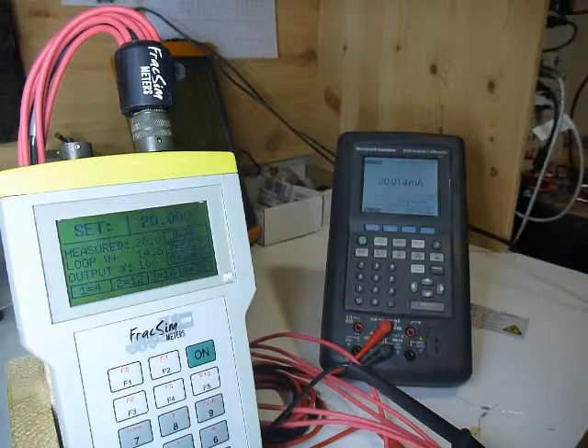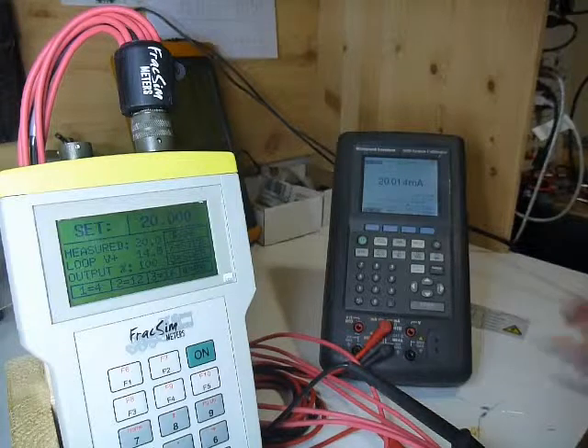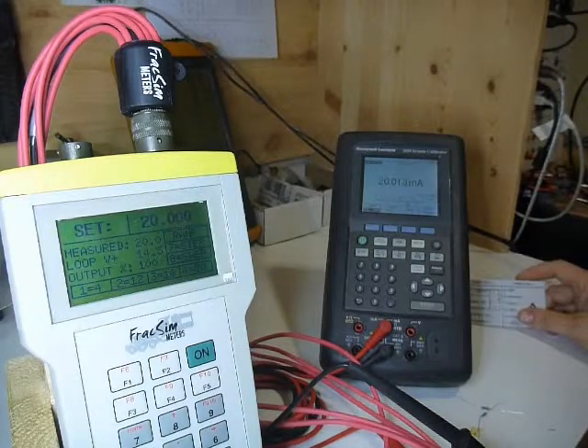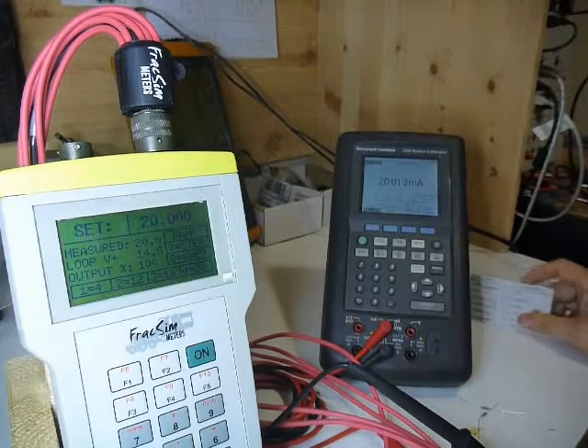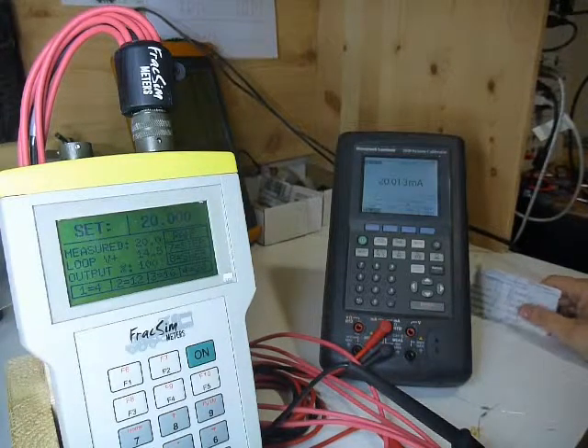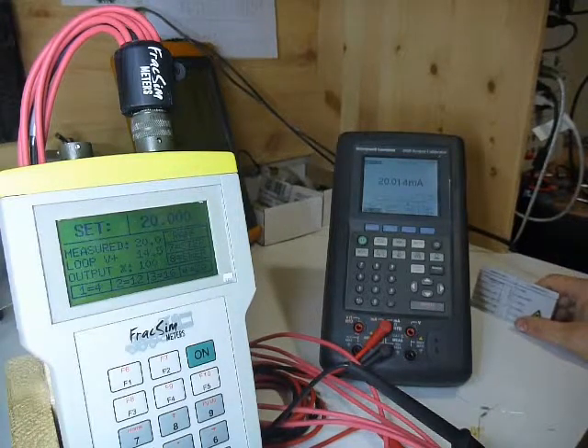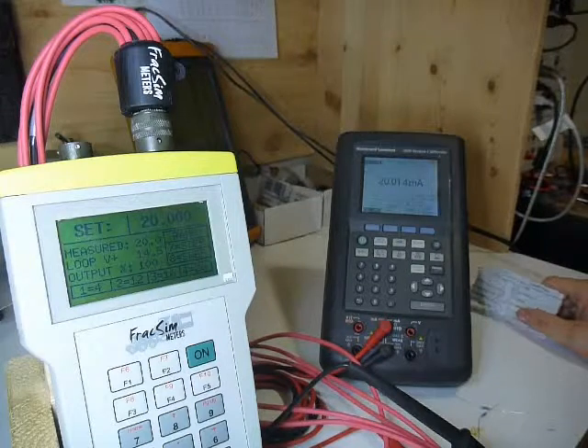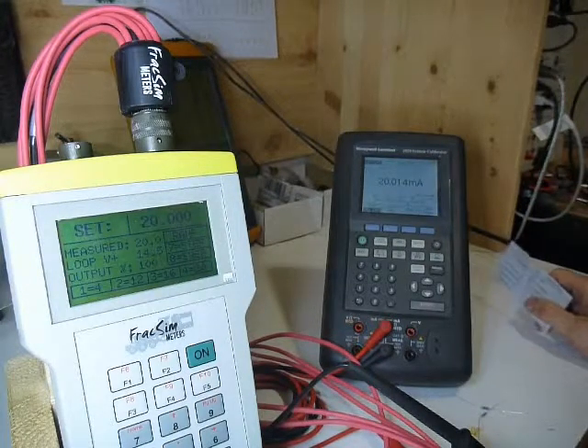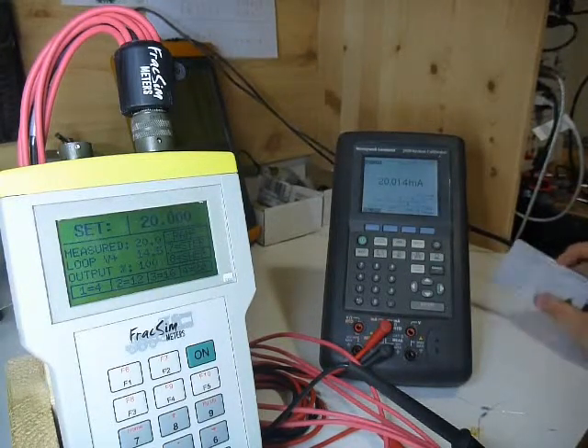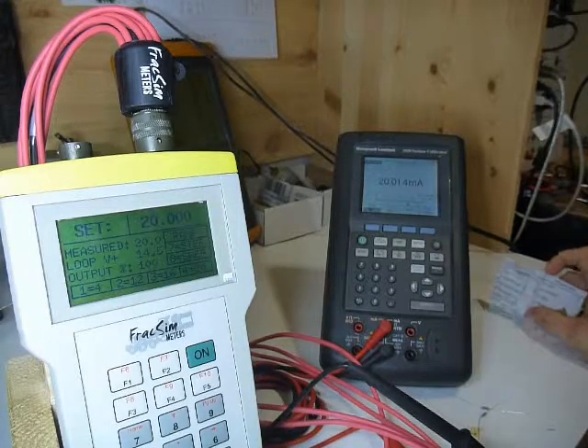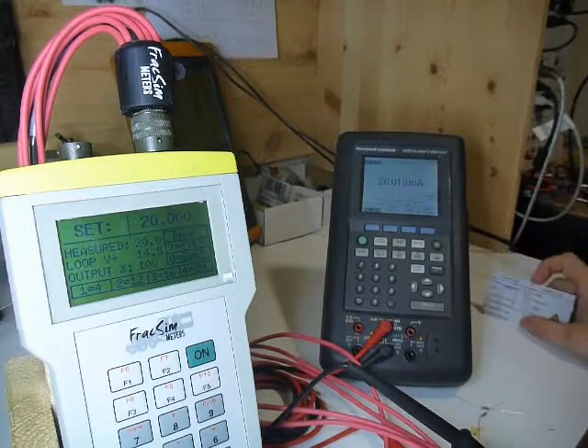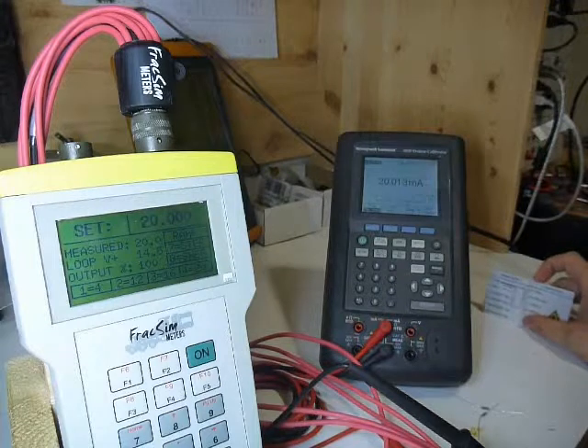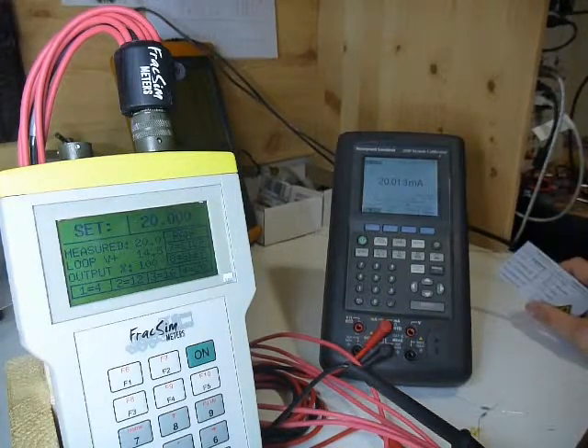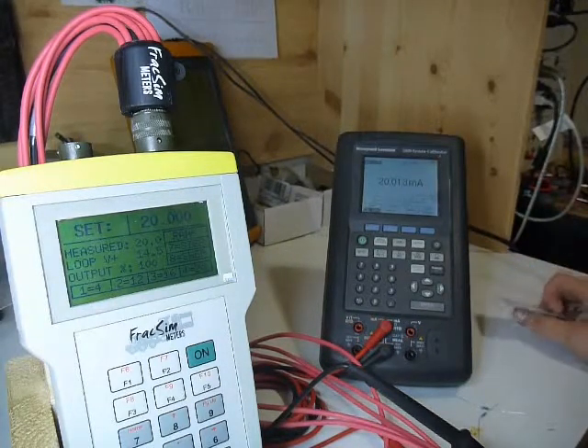So now again, what I wanted to talk about, the last piece here, is the 3-wire current sim. Now the 3-wire current sim is pretty unique. I've never seen another meter with that function. Basically, if you have ever had to simulate current and you want to measure voltage at the same time, the reason you want to do that is because you're having an issue and you're simulating and you just can't seem to figure it out, and you want to make a voltage measurement to see if there actually is proper voltage there.